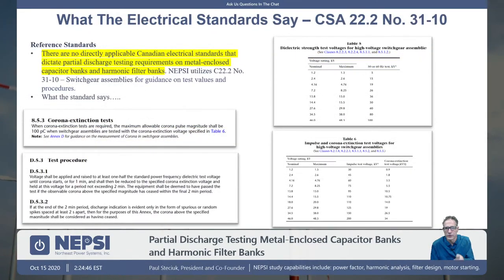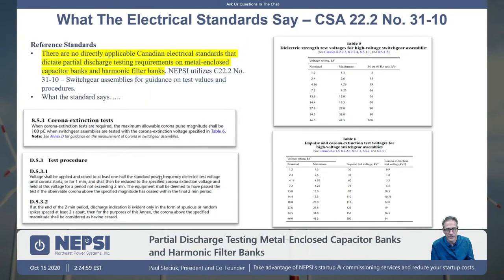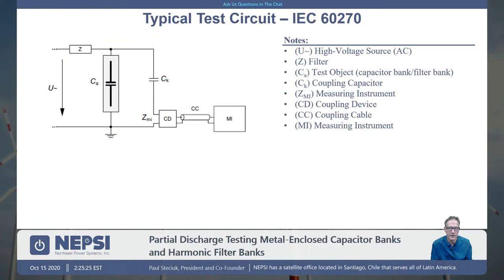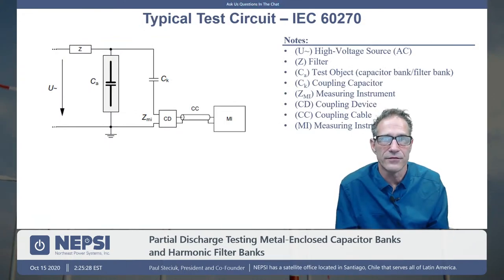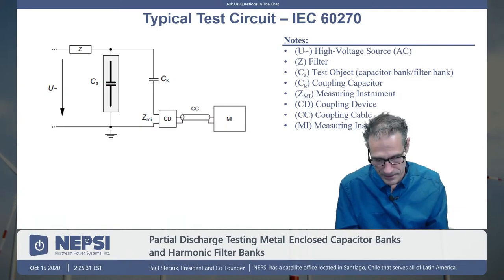There's another standard that we often have to go to, CSA standard C22.2 No. 31-10. And it's very similar. We have a different table, a slightly different set of values, a slightly different procedure. But overall, we're basically bringing the voltage up, going into corona, going to partial discharge, then dropping our voltage down, and making sure that our partial discharge level at the extinction voltage, or the partial discharge voltage as the standard says, that our picocoulombs, the actual partial discharge value, is below that value. I think that's clear.